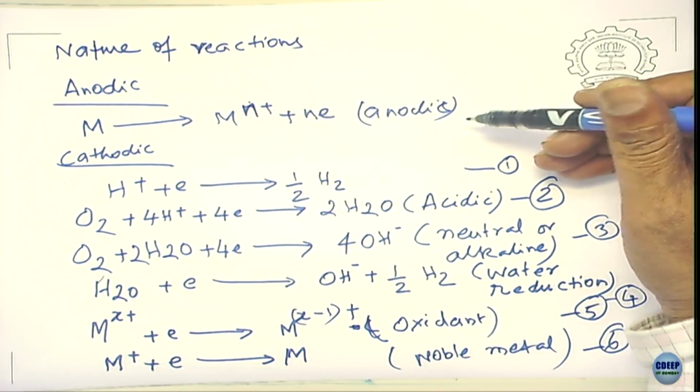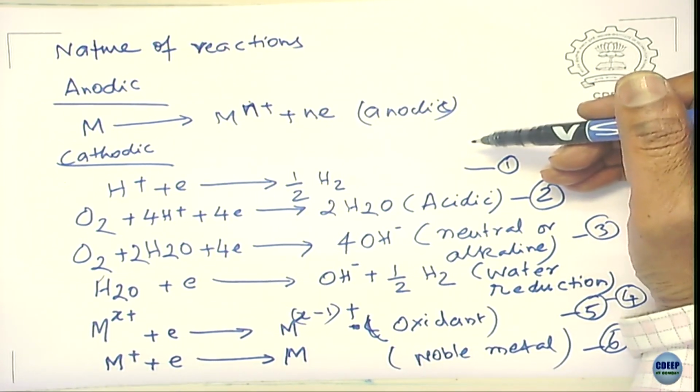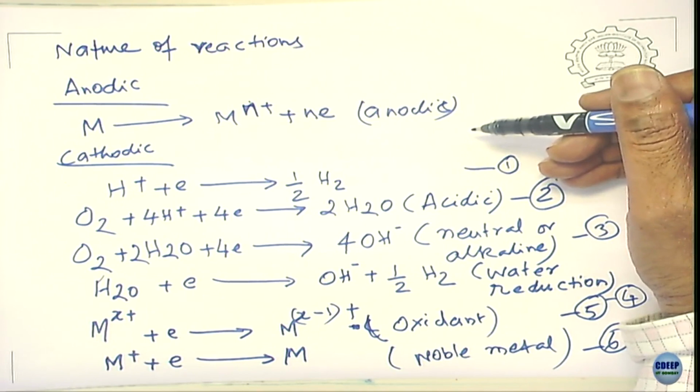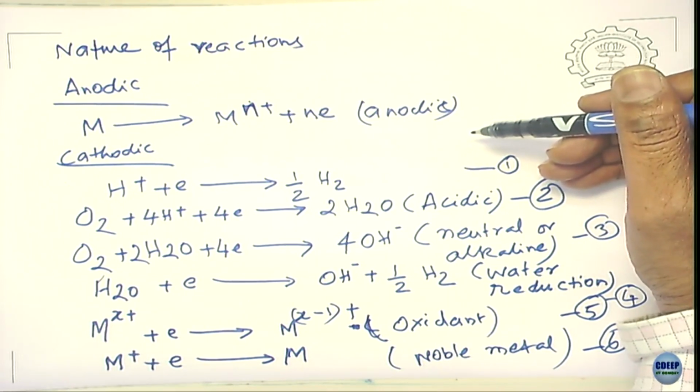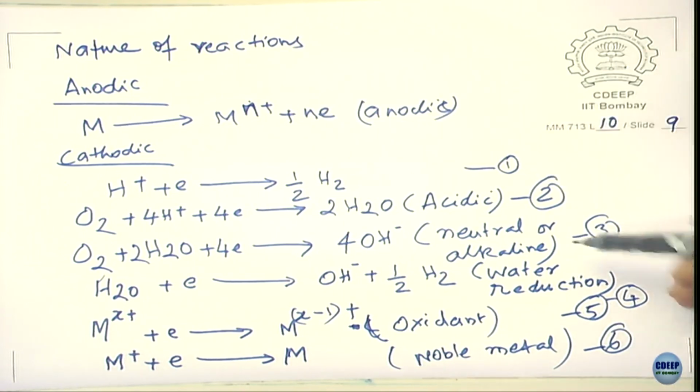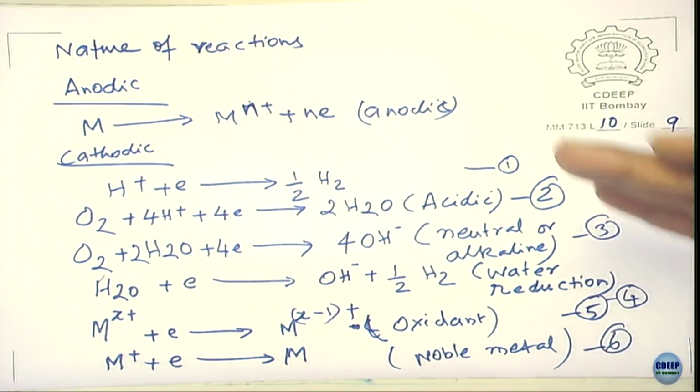You can make the metal passive. Now you have seen the Pourbaix diagram before, right. What the Pourbaix diagram is? It is a potential-pH diagram. If the pH is slightly alkaline, the metal can form passive films. So you form a passive film, you remove these things. So what happens? The steel can last for 25, 30 years at that temperature with the water, no corrosion problems at all actually.